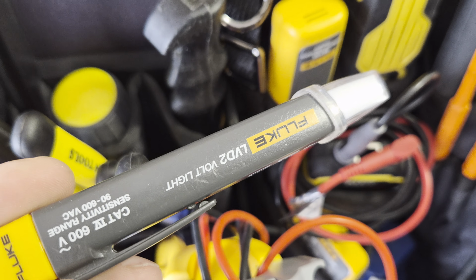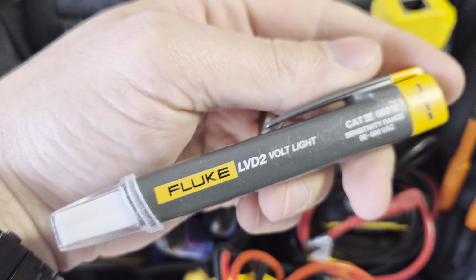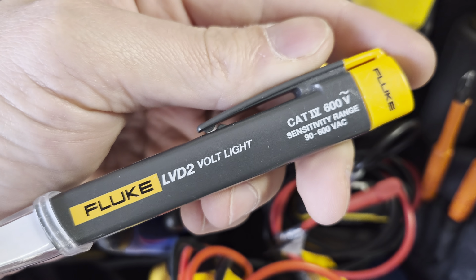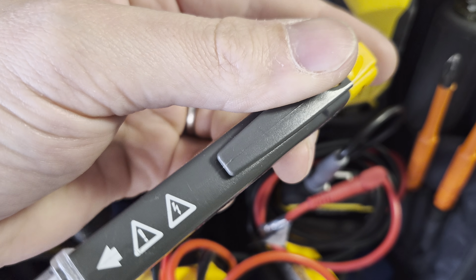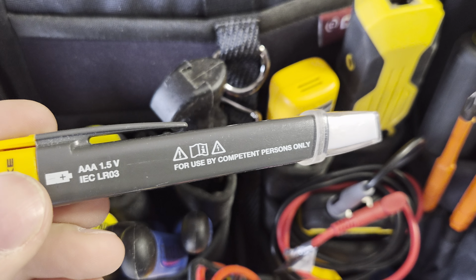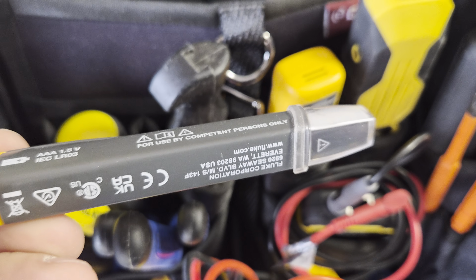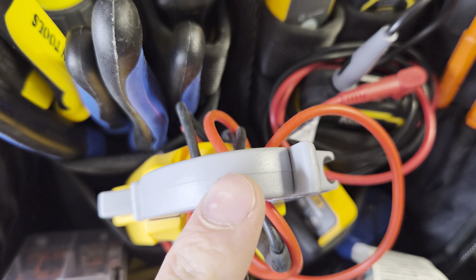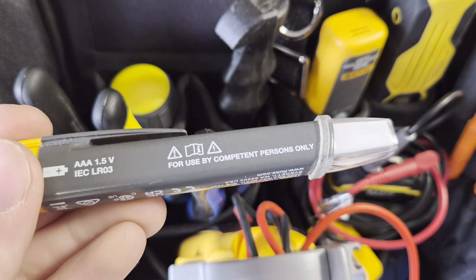A little Fluke right here. This thing detects the presence of voltage. It does not test the absence, it detects the presence. Don't use this and trust your life with it. Just verify you have voltage, shut the power off, then verify you have voltage when you turn it back on. Now you know you found the circuit. Use a multimeter to verify the absence of voltage. This only detects the presence.